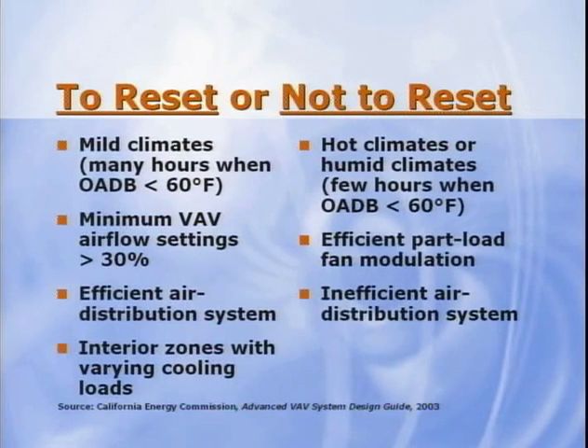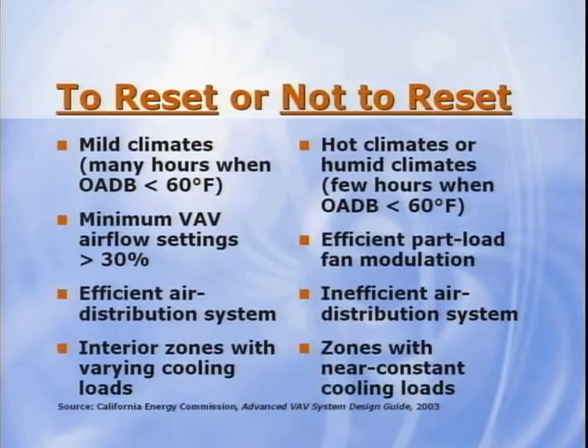Inefficient air distribution system design and systems that serve some zones that have nearly constant cooling loads. These zones will need design airflow during all occupied hours, limiting the ability to raise the supply air temperature. Investigate using a separate system to serve these zones.